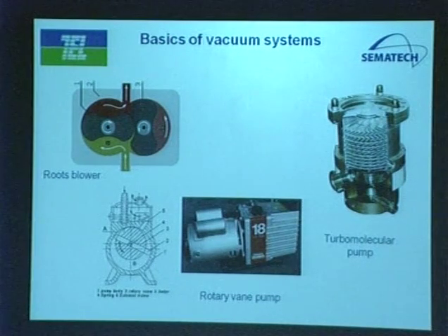This is so interesting, even though it looks very dry. Imagine these things suck air or gas from a system, but this pushes molecules. It's interesting that this can achieve 1 torr, 900 millitorr, while these can achieve 10 to the power minus 6 torr. It's almost like space, or the kind of pressure that can be generated in your chamber.